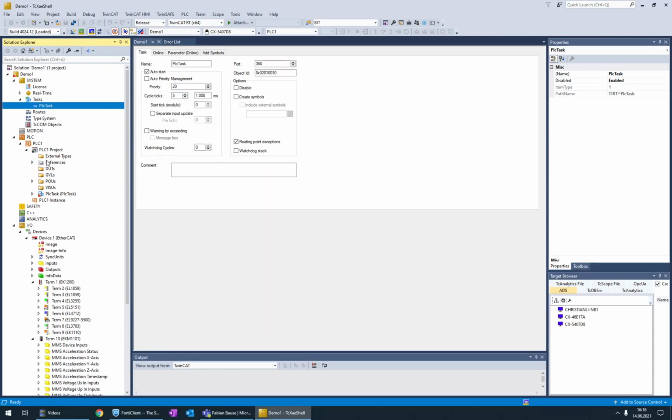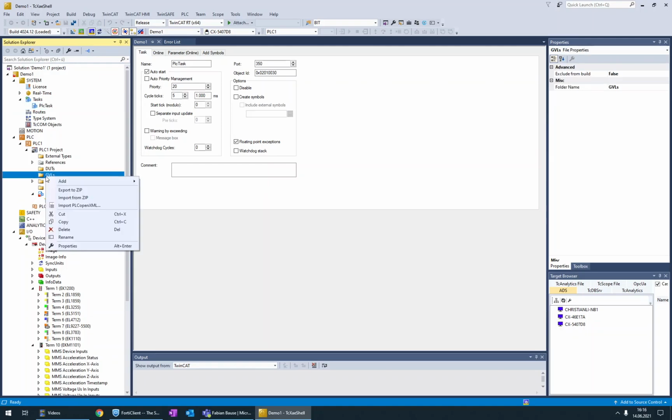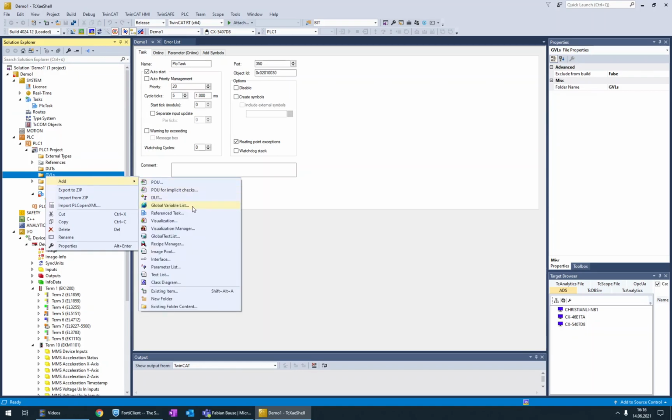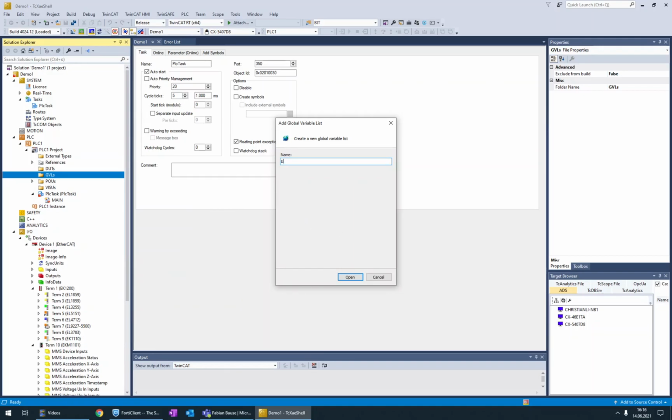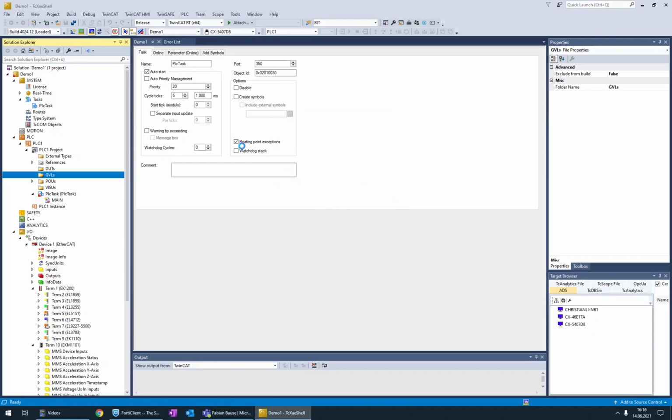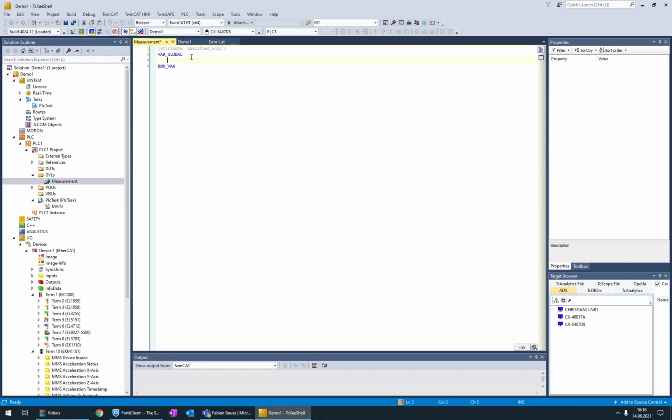And to have the configuration, so the link between the IO world and the PLC program, we create, usually one is doing something like the GVL, global variable list, and in this GVL some measurement terminals, so you can group different IOs to specific groups. I will have this EL3751 terminal, and this is an input. This input configuration at %I* is defined as an array from 0 to 9, so a full number of 10 values of DINTs, because this terminal is delivering data in DINTs. So that's all we need to do at the moment.